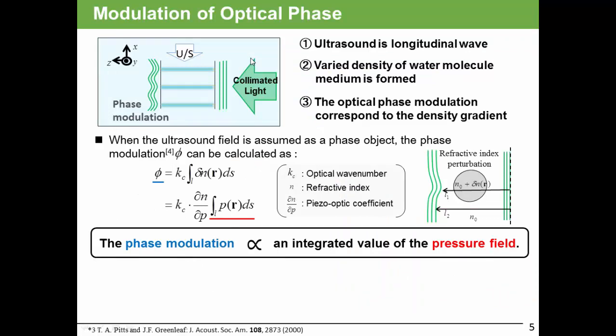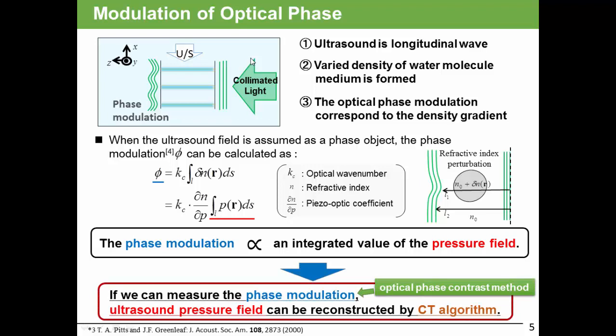Let me explain the modulation of optical phase. Ultrasound is longitudinal waves. So, when it propagates through the water, various density of the water molecule mediums is formed. When the collimated light passes through this medium, the optical phase modulation corresponds to the density gradient. When the ultrasound field is assumed as the phase object, the phase modulation can be calculated at this equation. The phase modulation is proportional to an integral value of the pressure field. So, if we can measure the phase modulation by using optical phase contrast method, ultrasound pressure fields can be reconstructed by CT algorithm.